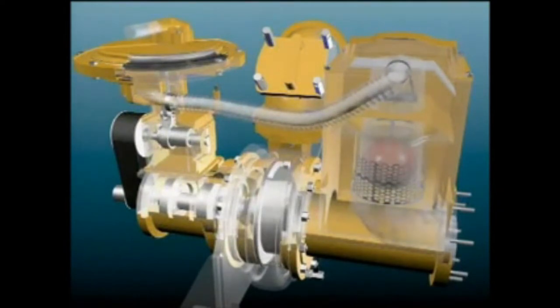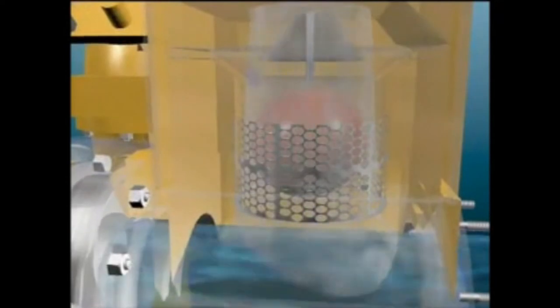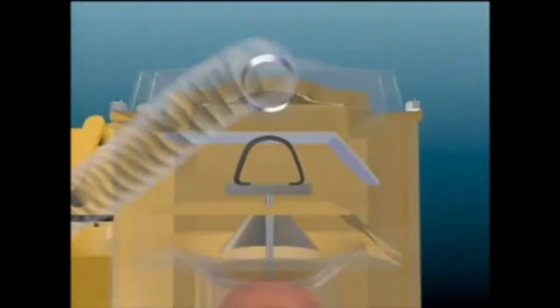Once a level of liquid has entered the suction chamber the float lifts and positively locates within the cone. This action also closes the rubber peel valve at the top of the float limiting the potential for liquid carryover.